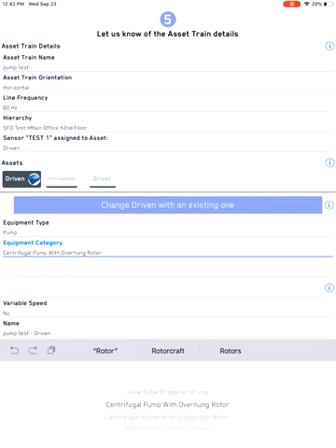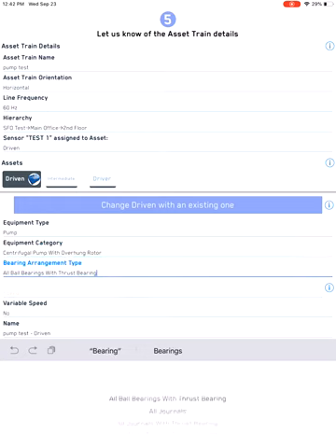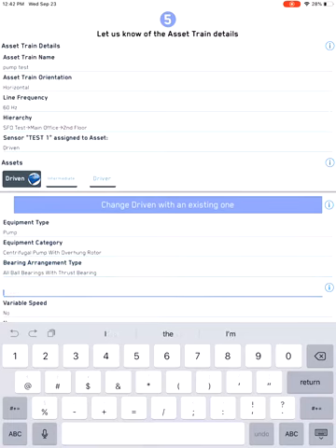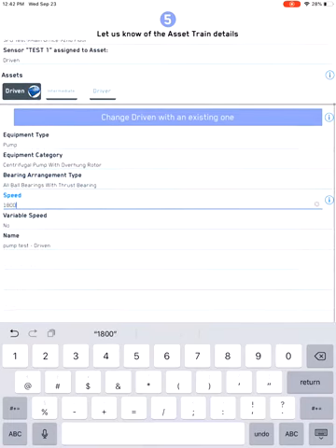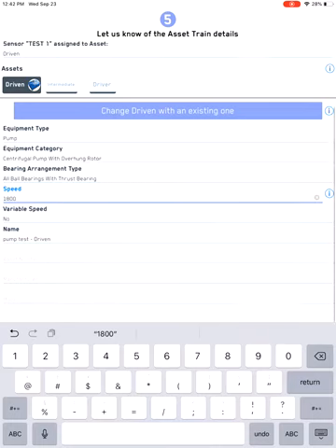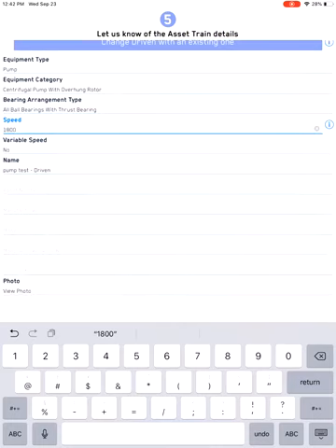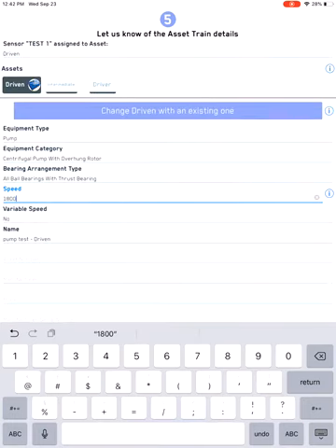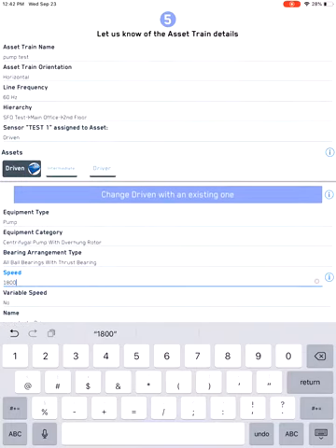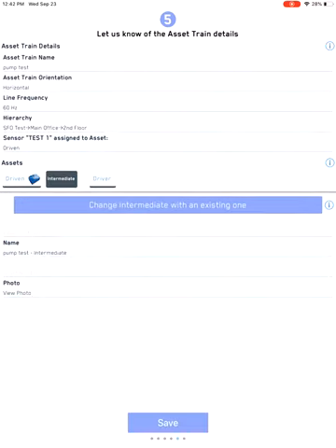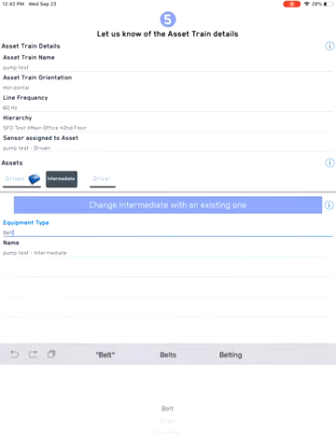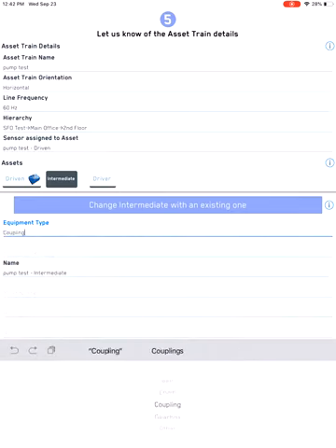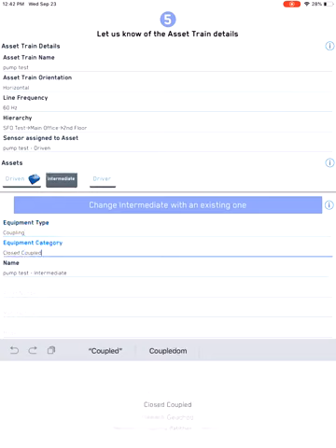Once you have done that, you want to then define what the bearing arrangement is and then the speed. So all this information is very critical for our diagnostics to work proper, but there's other information that you can fill in here that can make it even more accurate. But at the same time, there are mandatory fields. So once you're done filling this out, when you click save, if it says that you need to fill this particular information out, those are the mandatory fields. But then you might see the intermediate, driver, and driven show a yellow color meaning it's not completely filled, but it will still run the diagnostics.